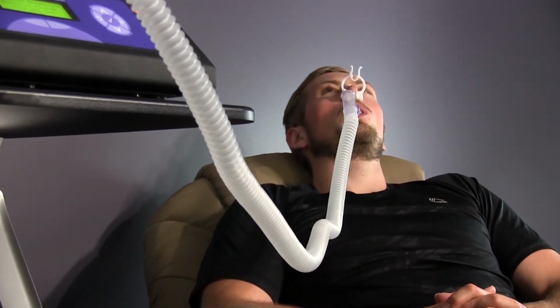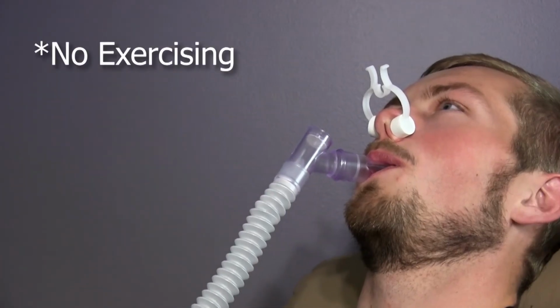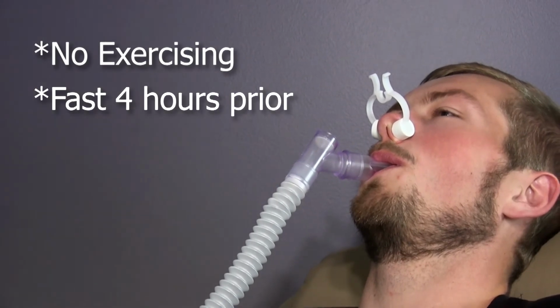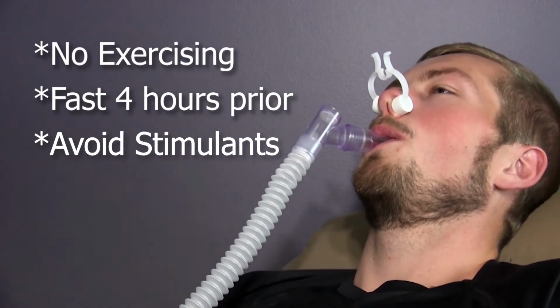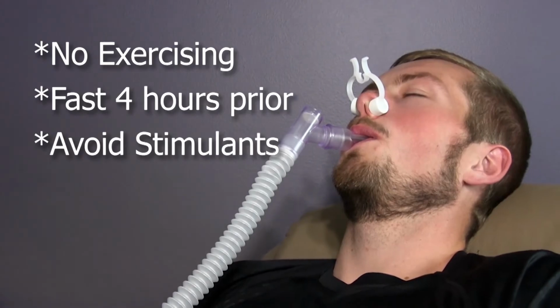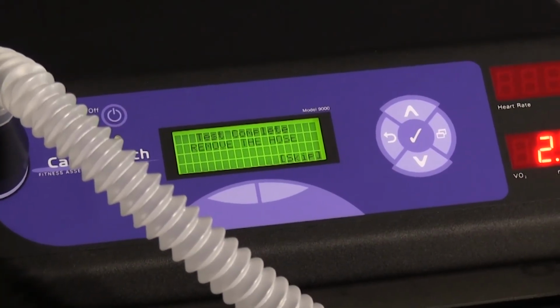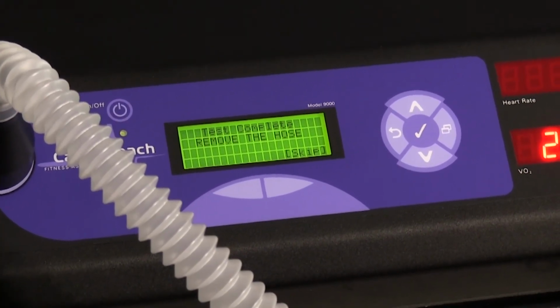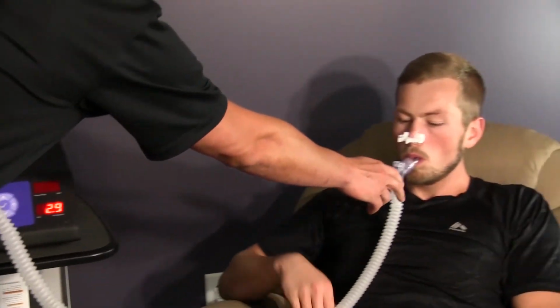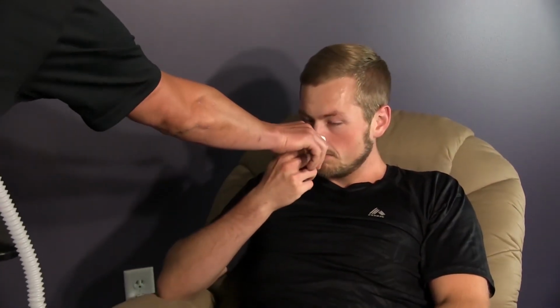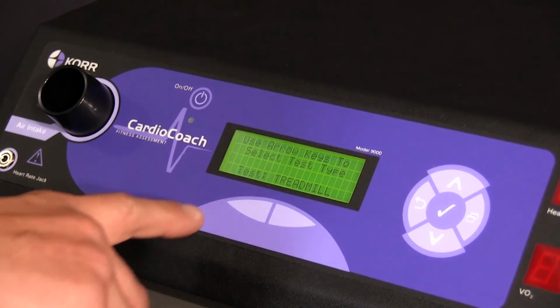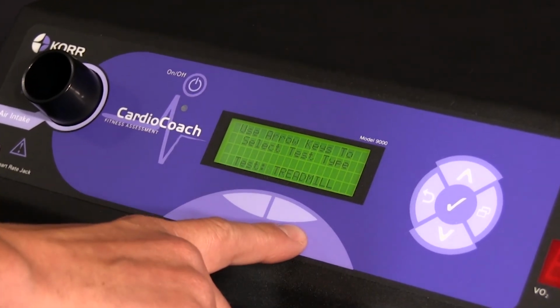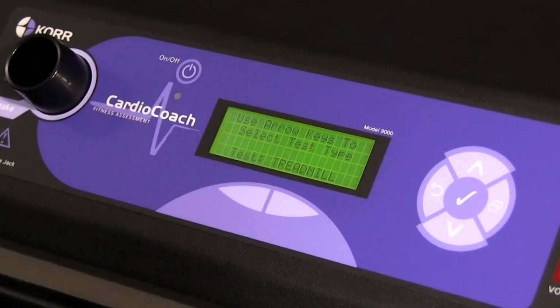Test results will be most accurate if the client comes prepared by not exercising the day of the testing, fasting 4 hours prior to testing, and avoiding stimulants. When the test is complete, the unit will beep. Disconnect the metabreather tubing and throw it away. You can print the results using the soft keys below the LCD screen. After the results have printed, you will be ready to interpret the results for your clients.